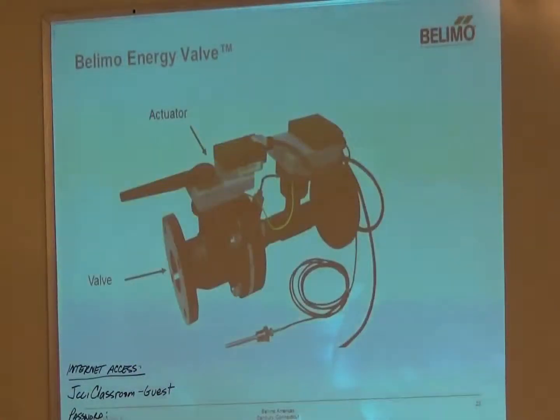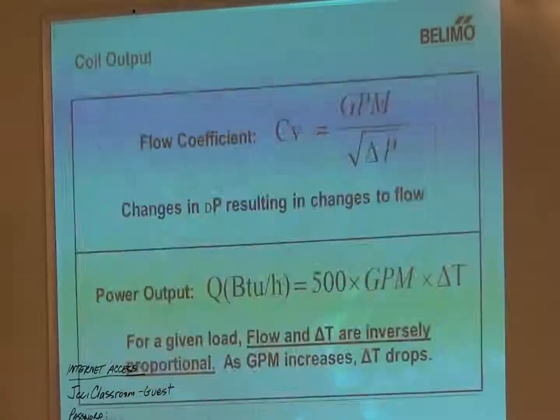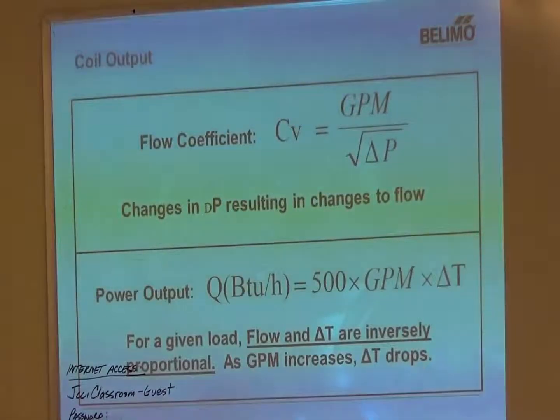So that makes the formula Q equals 500 times your GPM times delta T. As that GPM changes, it's looking at that whole equation to get the Q, or the BTU output. So it's never controlling on flow? I'm just trying to make sure I have it clear how it works. If it was not operating in power control, just operating as a standard, what we call flow control, then yes. You can set it up either way.